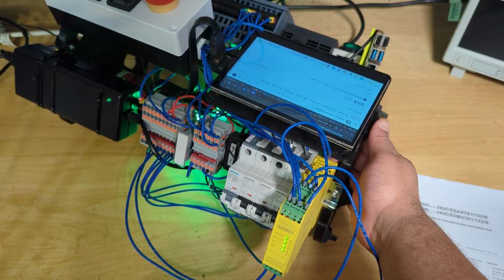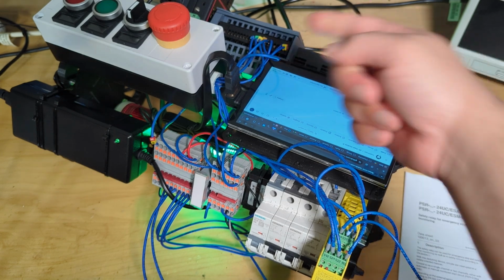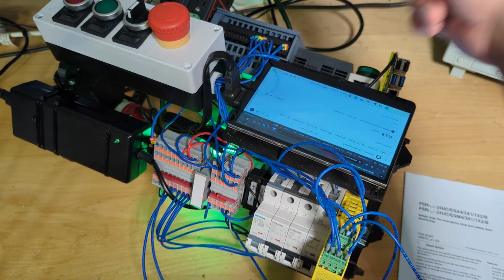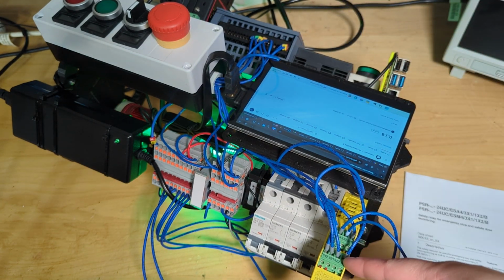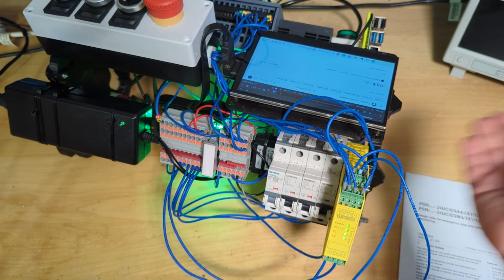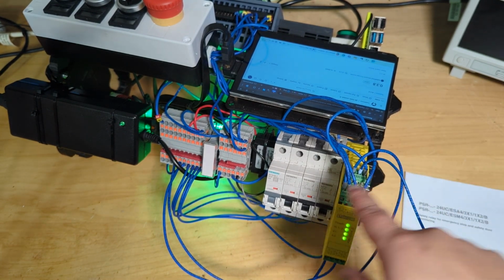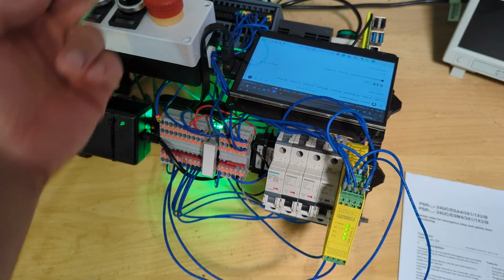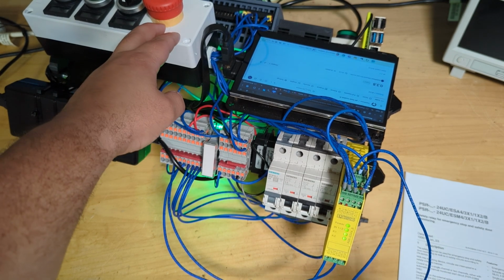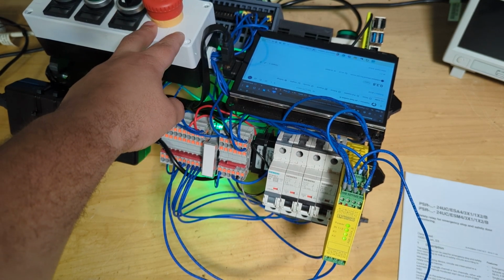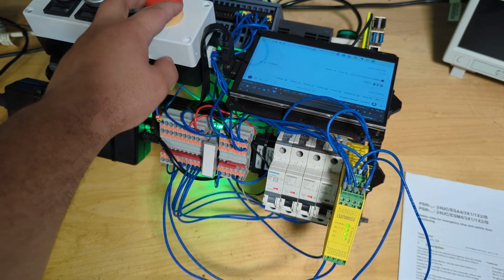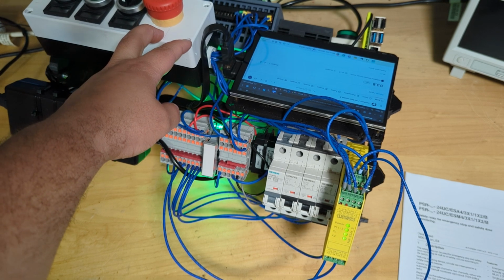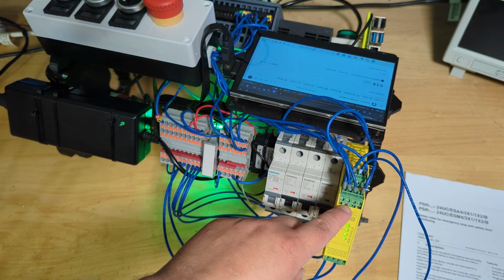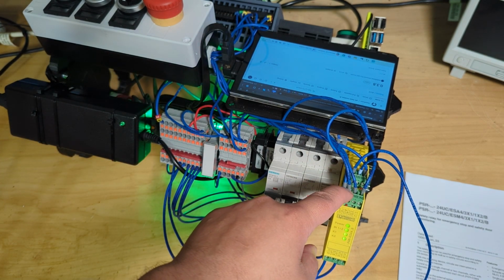If you've got money to spend and you've got the budget, you're going to go with a safety PLC. So this is a non-safe PLC, hence I'm using a safety relay, because it's cheaper. Essentially they both do the same thing. E-stops, you should know, are two channel devices, or should be two channel devices. You've got two normally closed channels coming into the control system, in this case, into my safety relay.